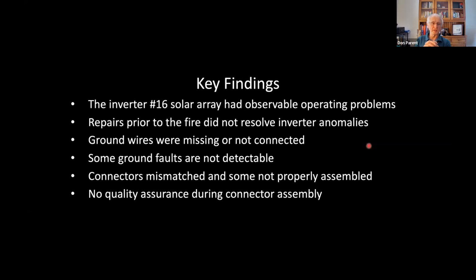I should also mention that some ground faults are not detectable. Number one, it depends where they are. If they're upstream of the combiner boxes, sometimes you can't detect those. But also the ground fault has to be in excess of 5 amps because the detection breaker is 5 amps. So if you have 4 amps, the inverter is just going to continue operating. There were mismatched connectors and there were corroded connectors.